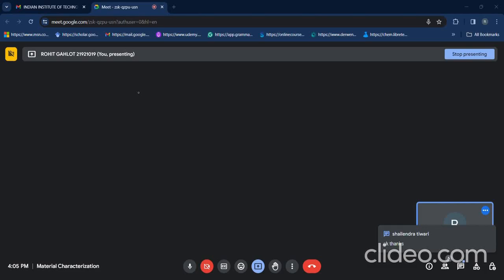In one lecture, the difference between the different currents, like beam current and probe current, was also taught. When your electron beam comes in contact with different lenses and apertures, then your current significantly reduces. So it is not that your beam current is similar to the probe current. I think you already know. So the portion of the electron current that leaves the gun through the hole in the anode is called the beam current.